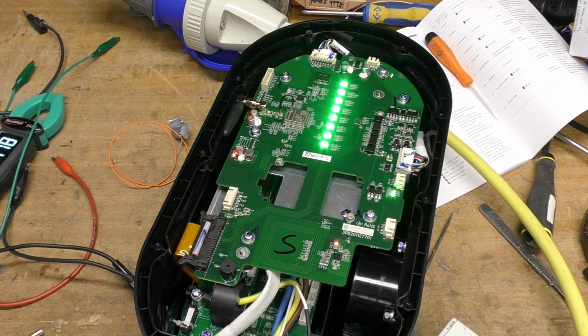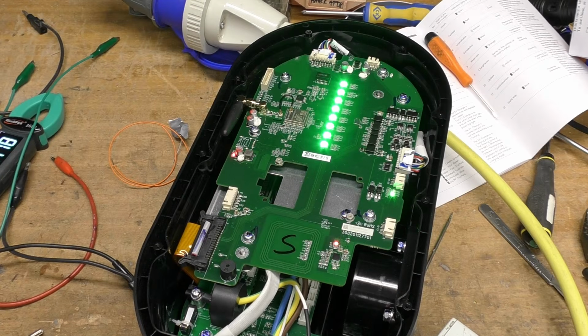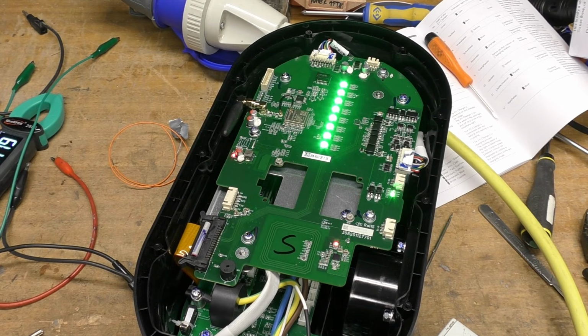Different countries have different systems. I think there are other countries where this is also applicable, but this is why that protection is specific to the UK. It's written into the BS 7671 wiring regulations. And what it means essentially is that when the supply comes into the house, earth that goes to the house wiring is actually connected to the neutral at the point where it enters the house. This means that if there's a fault upstream in the road somewhere and the neutral becomes disconnected, the earth terminal can actually become live.